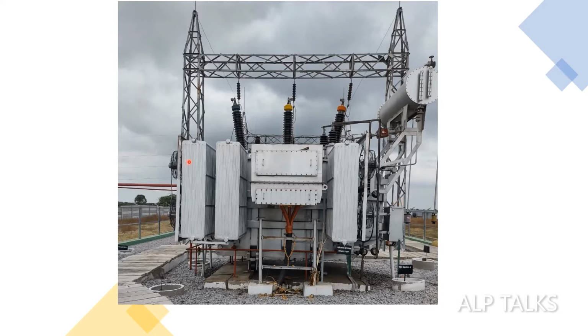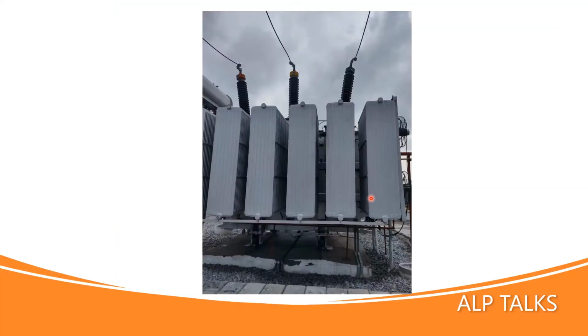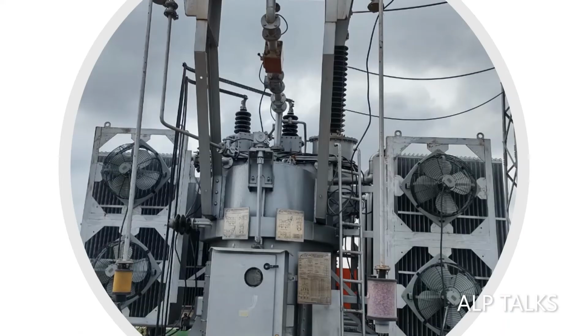I think we have fans only on one side of this power transformer. We have a conservator arrangement here. On this conservator we have two oil level gauges, which we can observe here. It may have an air cell otherwise. So this is the radiator arrangement. This is another part of the power transformer, the marshalling box. Sorry, this is the control cabinet. It is an in-tank OLTC.